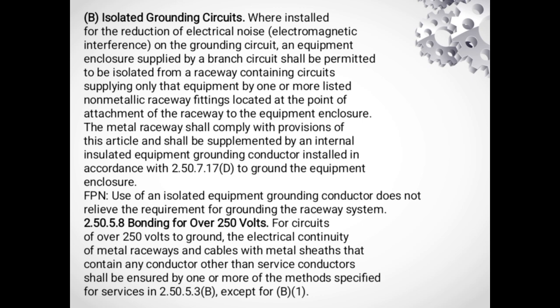Section 2.50.5.7 and 2.50.5.8 address specific bonding requirements for isolated grounding circuit and system operating over 250 volts. Isolated grounding circuit require careful attention to minimize electrical noise. System over 250 volts demand robust bonding to handle potentially higher fault currents.